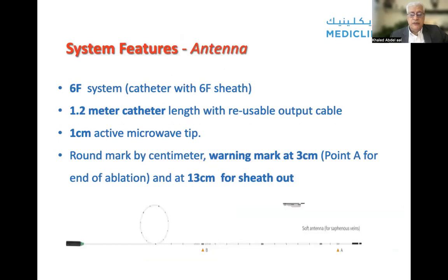The system is a low profile system. It uses 6 French sheaths. After introducing the sheath, you introduce the catheter inside the sheath. This catheter measures 1.2 meters in length. At the last 1 centimeter, you have the active microwave tip that delivers the energy.